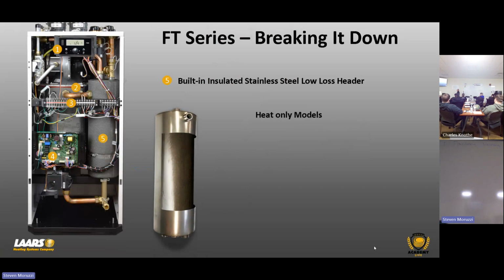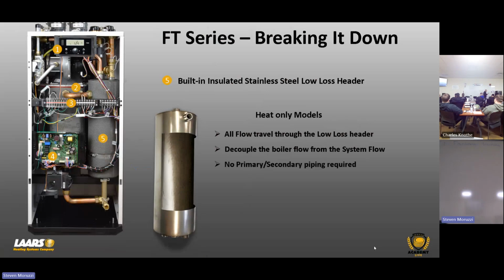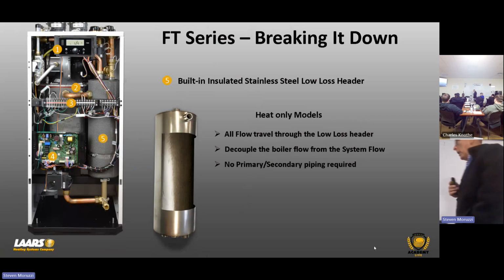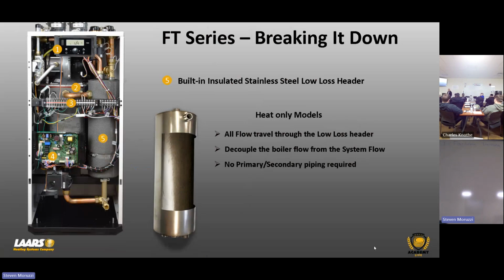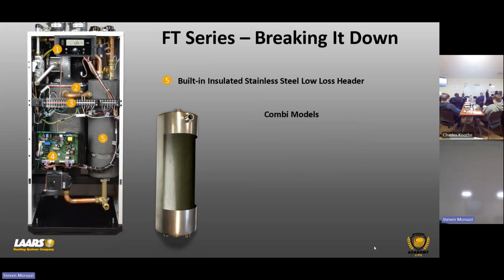On the heat only models, it's an empty shell, stainless steel, all welded, no gaskets, other than the connection points. But on the combi, all flow travels through the low loss header. We're decoupling the system from the boiler loop, guaranteeing proper flow. By doing this, we no longer need primary, secondary. So you can rip out an old cast iron boiler and that replacement that was series piped, boiler flow in, out, okay? Rip that out, and you can connect this now without having to go primary, secondary. You can do either or, all right? We have the valves for it, meaning the isolation valves, which we'll talk about. And we ensure low flow velocity, minimizing the pressure drop.